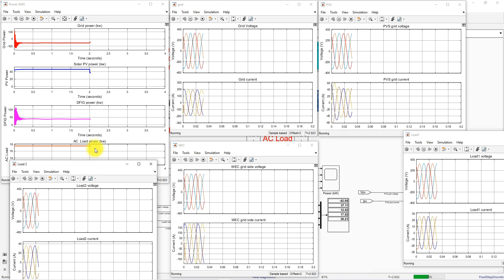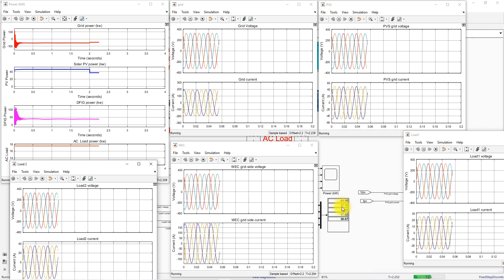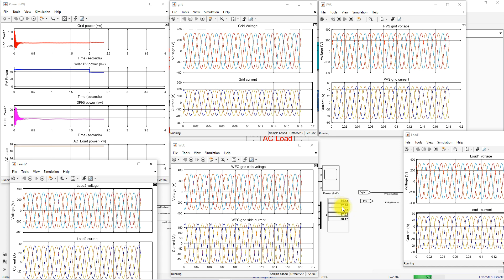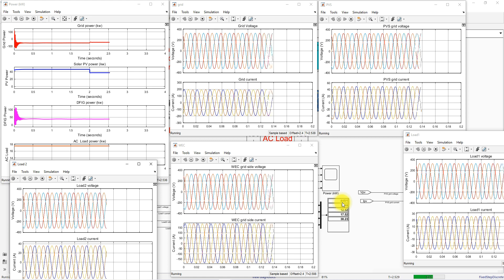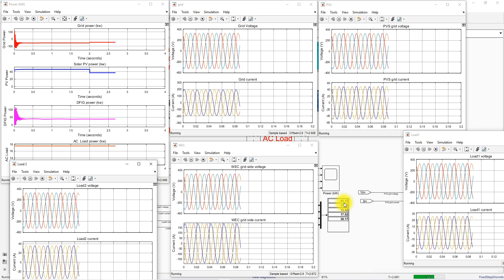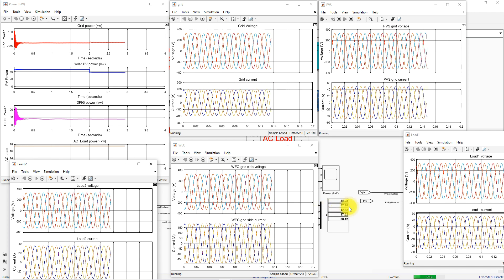You can see the variation after two seconds when irradiation changes from 1000 to 800 watts per meter square. Because of the reduction in irradiation, PV power generation drops from around 46 kilowatts to about 37 kilowatts. As a result, the excess power fed to the grid also reduces — the grid power changes from minus 53 kilowatts to minus 44 kilowatts. This shows that when the irradiation condition changes, the power sharing in the system automatically adjusts.